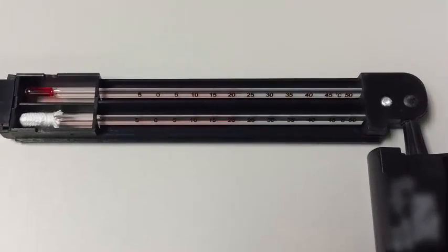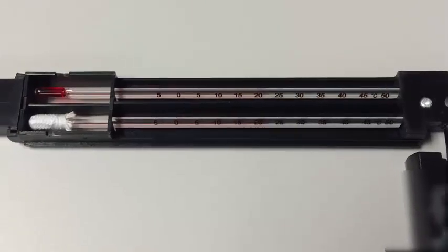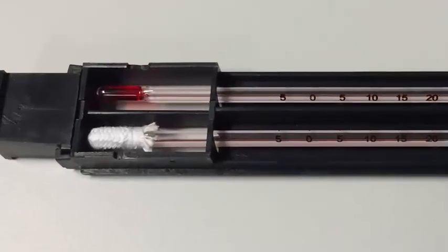This is a sling psychrometer. This is the instrument we're going to use to measure relative humidity and dew point temperature. This instrument is essentially just 2 thermometers on a stick, and they spin around. But one of those thermometers has a little piece of cloth on the end of it. What we do is we dip that piece of cloth in some water, and we spin this thing around.